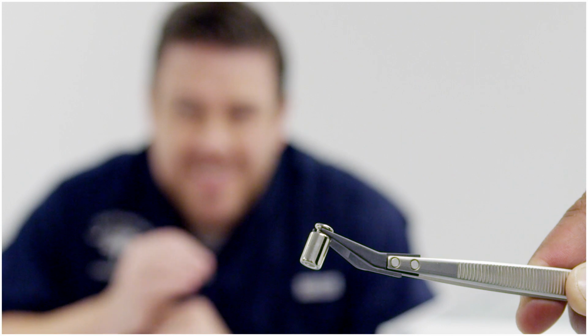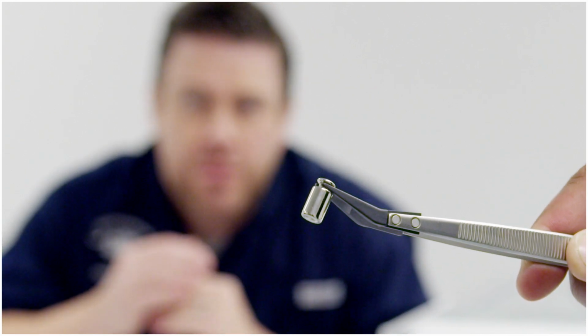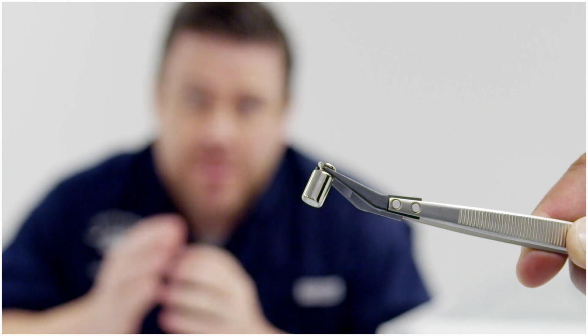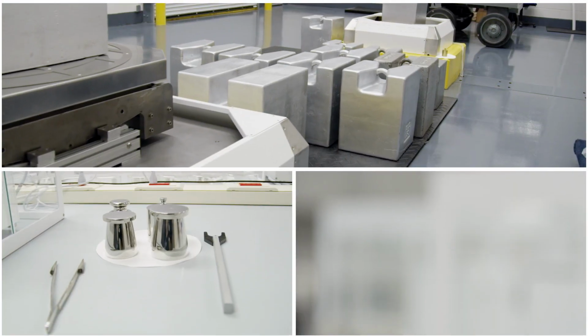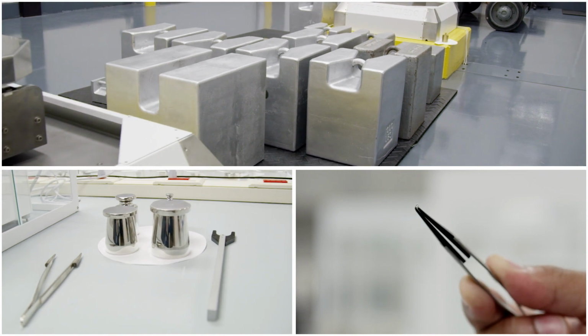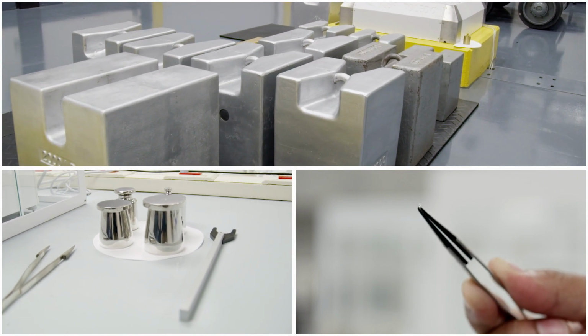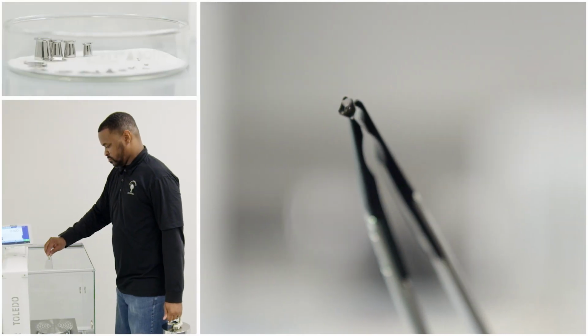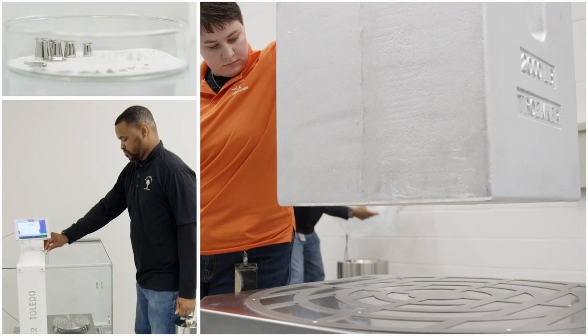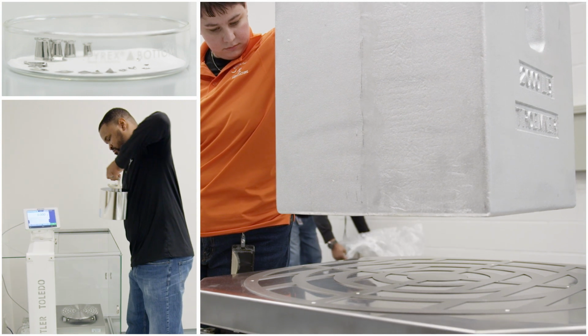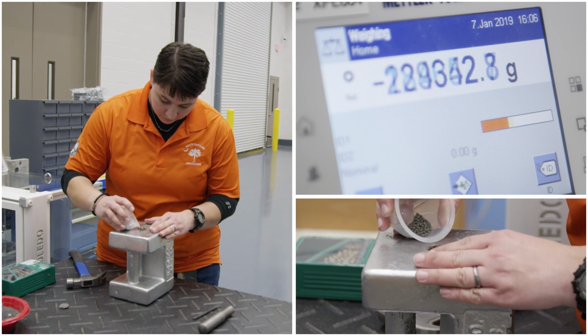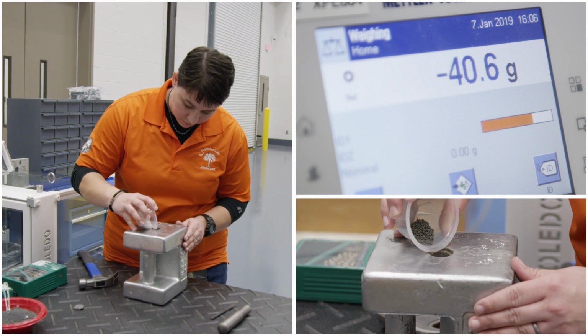For example, these tiny weights may be used by pharmaceutical companies or precision tool factories that must have the most accurate weights to ensure doses are exact, tools are calibrated accurately, and that container sizes are perfect. Every weight that comes into the lab is calibrated using different procedures, depending on the size and class of the weight, from the smallest, highly polished stainless steel weight to the heaviest cast iron weight. Each is compared to the laboratory's weight standards. If there's even the slightest discrepancy, the weight being tested will be modified using a substitution procedure.